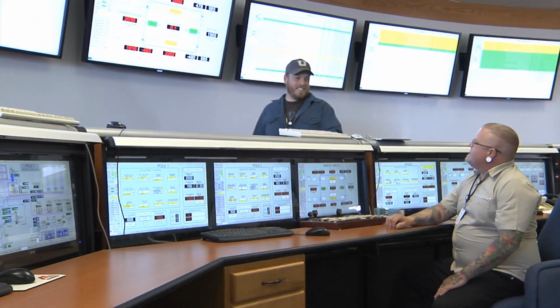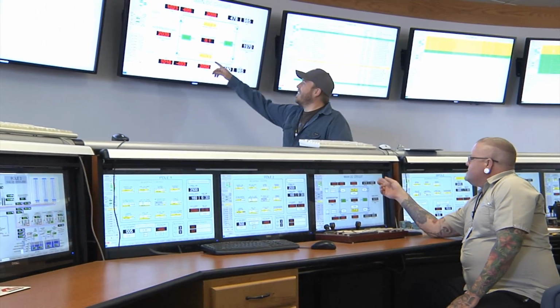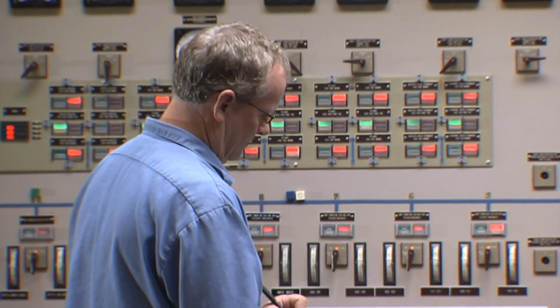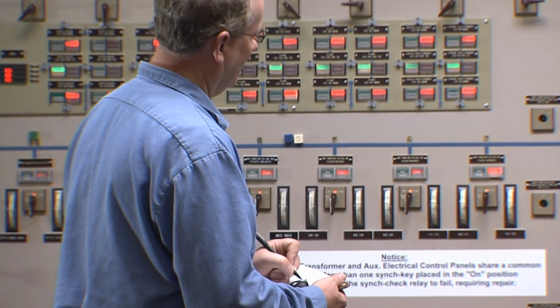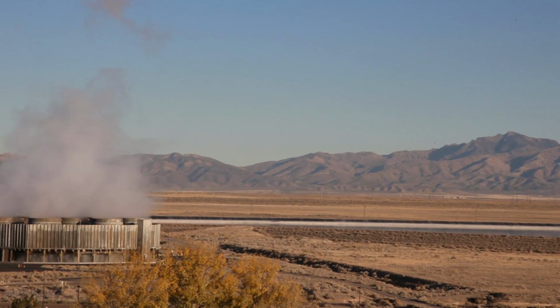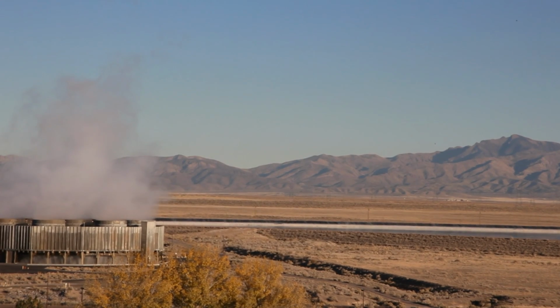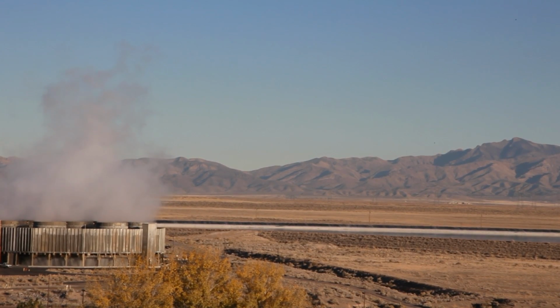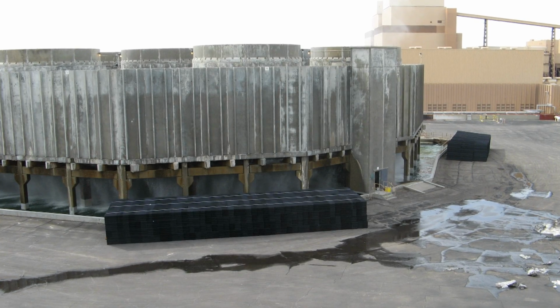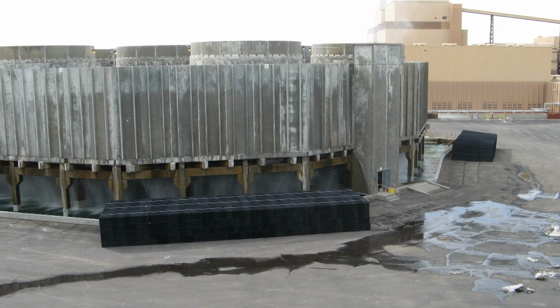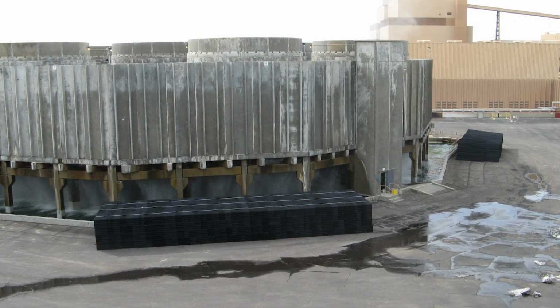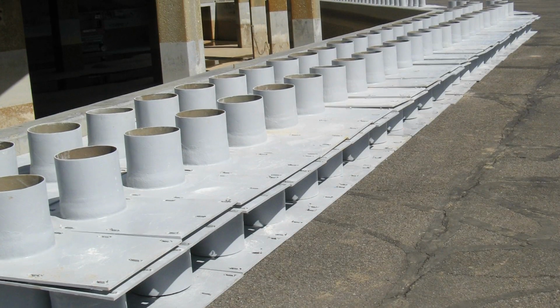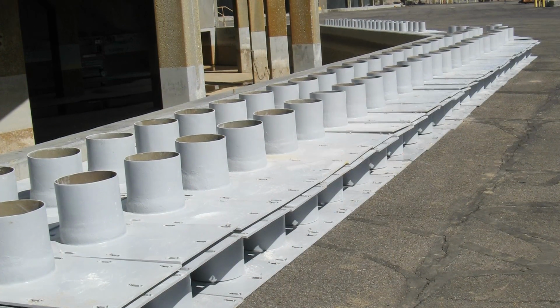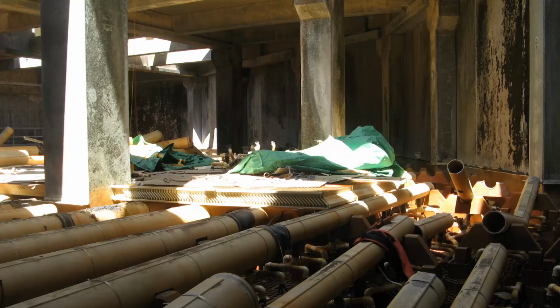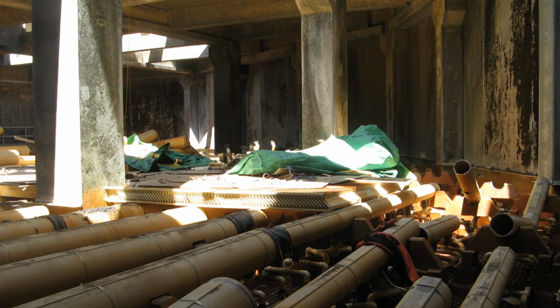Also contributing to this net unit heat rate improvement is the improved condenser back pressure, achieved by improving water flow characteristics through both unit cooling towers and reducing leakage of the water distribution system. High-energy steam drain piping in the condenser hot well was replaced, along with 2 water box expansion joints. Circulating water pipe sections were repaired with carbon fiber wraps. Circ water line thrust support was improved, along with cooling tower mechanical renovations.